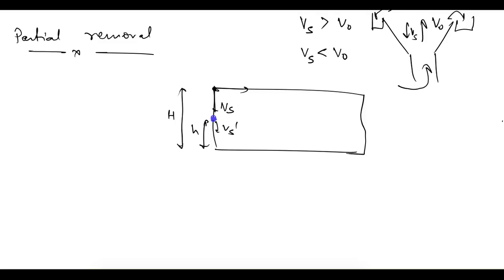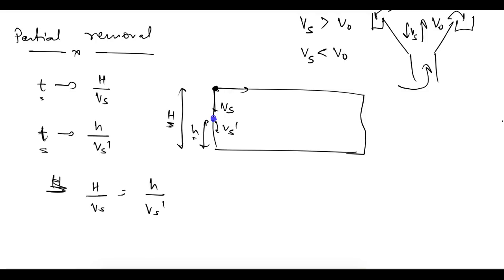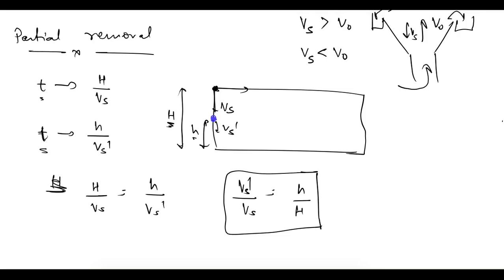In time t, a particle at the top with velocity Vs travels full depth H: t = H/Vs. In the same time t, a particle with velocity Vs' starting at height h travels distance h: t = h/Vs'. Equating both: H/Vs = h/Vs', which gives Vs'/Vs = h/H. This means a particle with smaller settling velocity Vs' will be removed if it starts at a proportionally smaller height h.